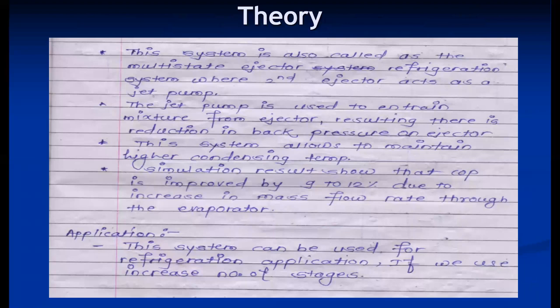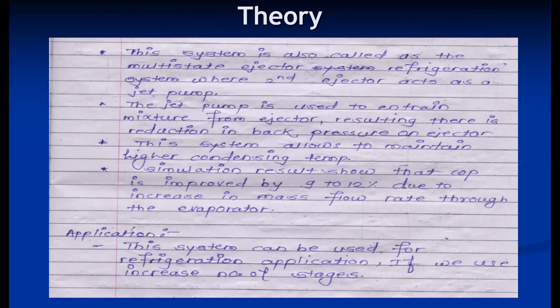This system can be used for refrigeration applications by increasing the number of ejector stages. The normal ejector refrigeration system is suitable for air conditioning applications, but with staging it can be extended to refrigeration. Main applications are for higher condensing temperature and refrigeration. With the jet pump, the entrainment ratio is increased, improving the COP by around 9 to 12 percent due to the increase in mass flow rate in the evaporator.